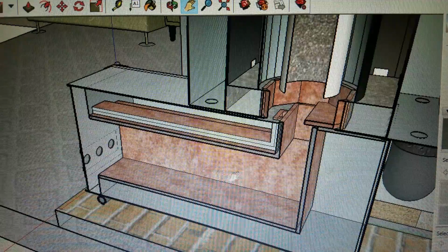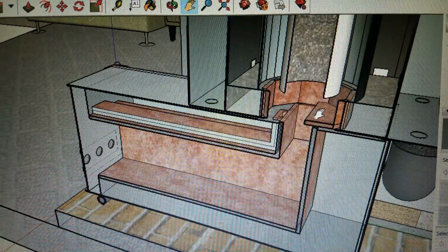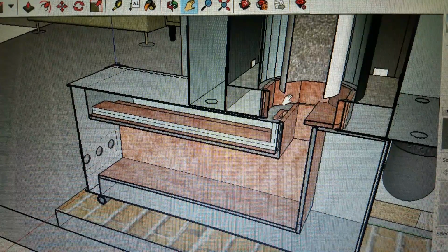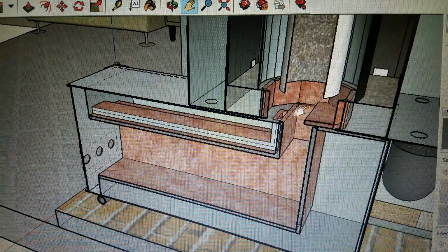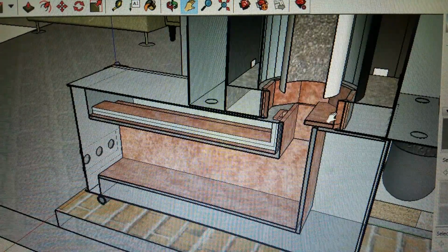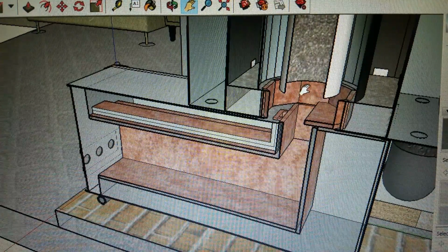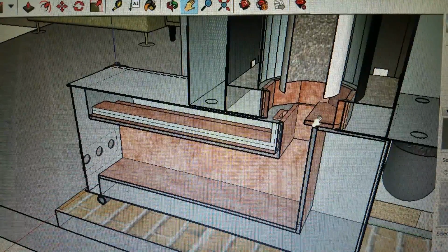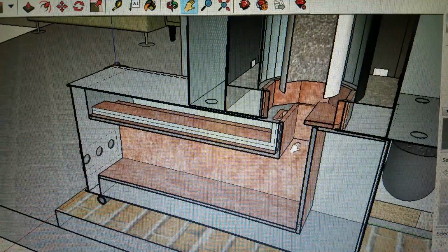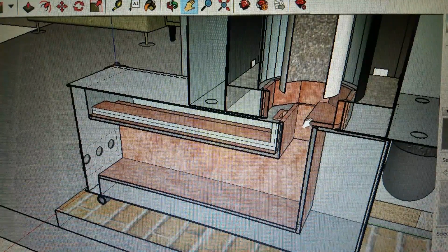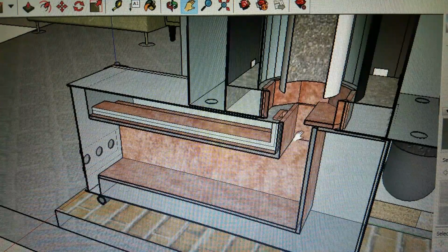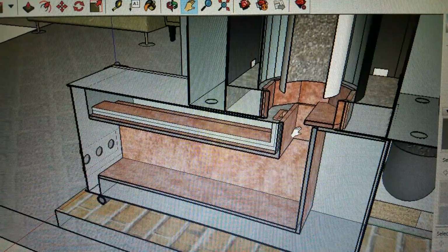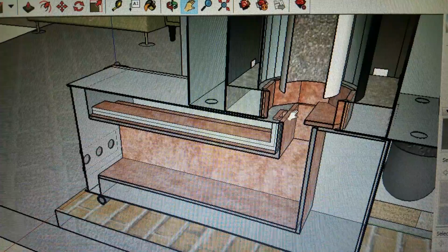Now, as the gases come up and go into that vortex area, that is like a wide spot in the river. It's going to slow down for a split second because there's way more cubic inches in there, because it's 6.5 inches in diameter versus the 4-inch riser. And also, you see this plate right here where the cursor is? That is a specific size plate that cuts down this area where the gases go up to a certain specific square inches. It's meant to cause turbulence and resistance.